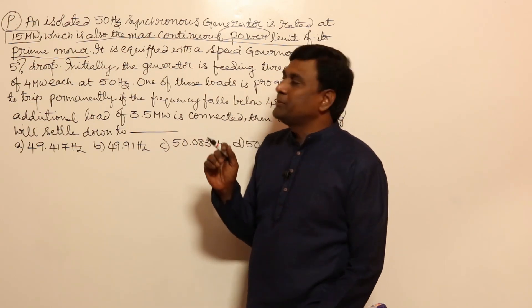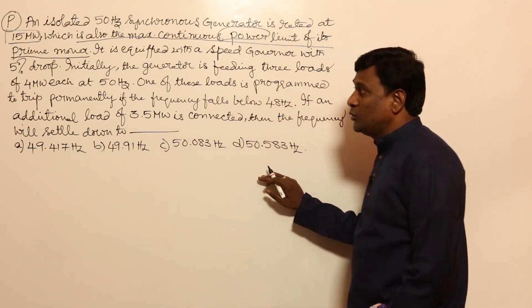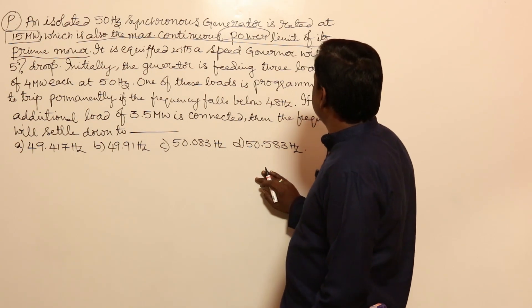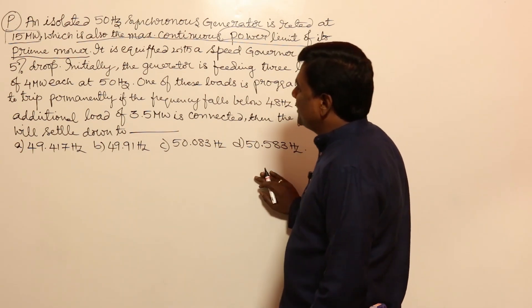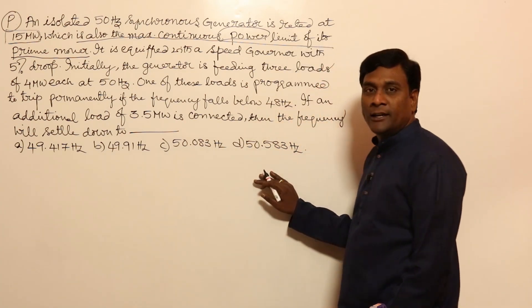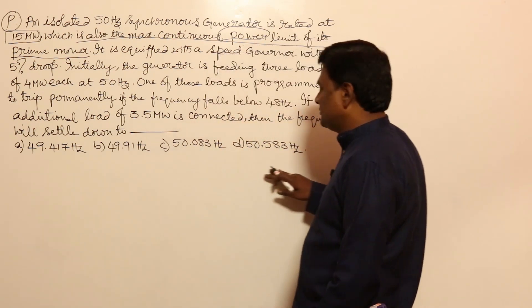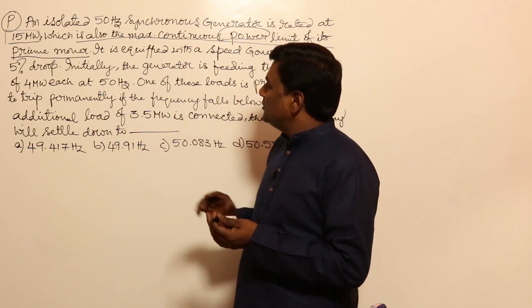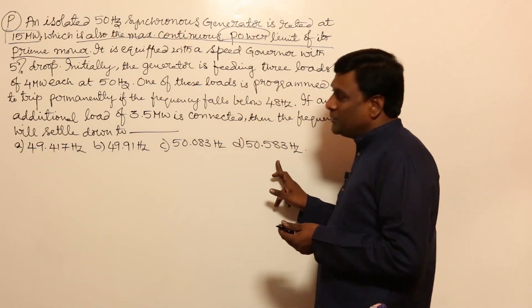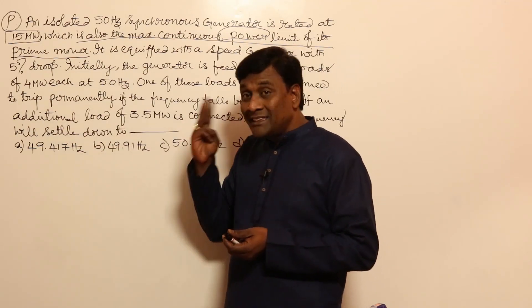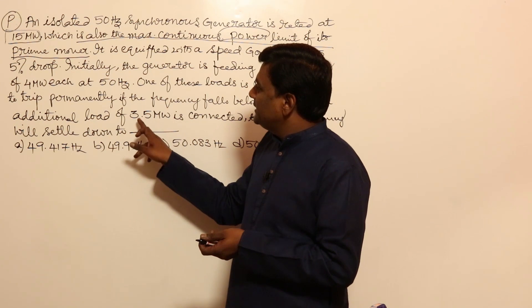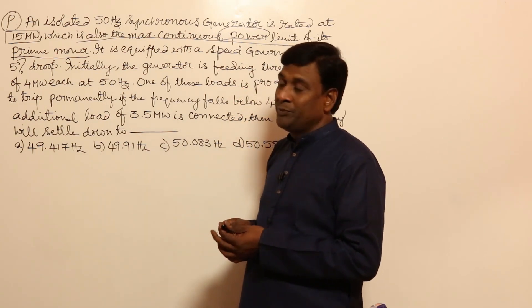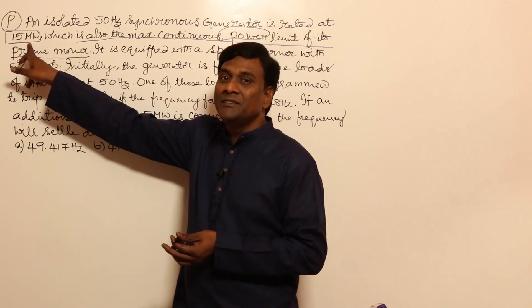The 15 MW generator has five percent droop characteristics. Initially the generator is feeding three loads of four megawatt each at 50 Hz. One of these loads is programmed to trip permanently if frequency falls below 48 Hz. An additional load of 3.5 megawatt is connected, so total load is 3×4 + 3.5 = 15.5 megawatt, exceeding the maximum capacity of 15 megawatt.